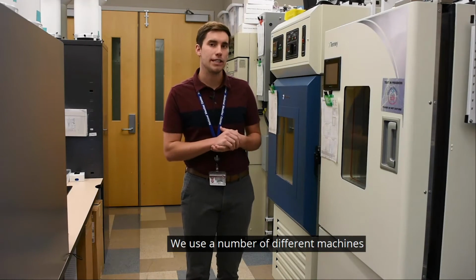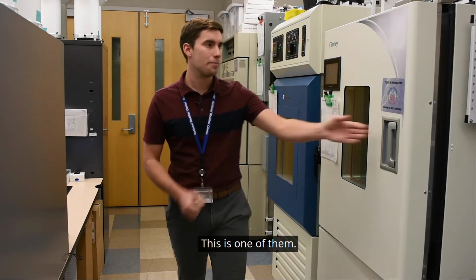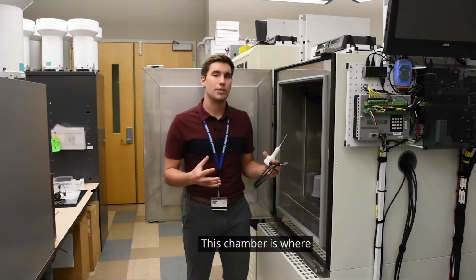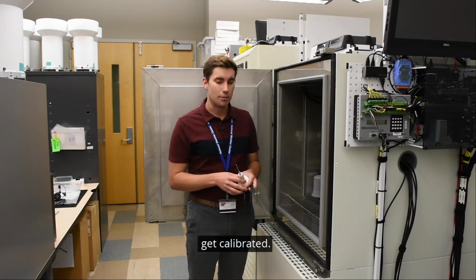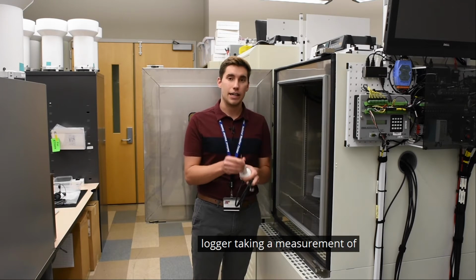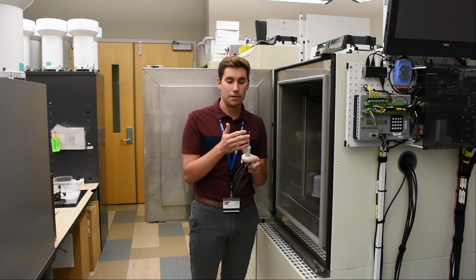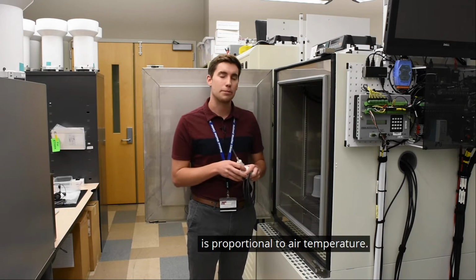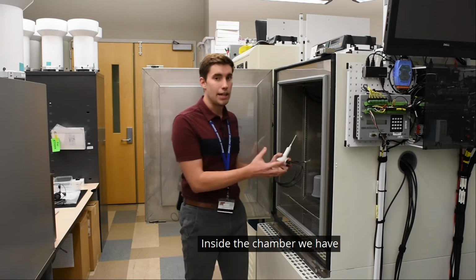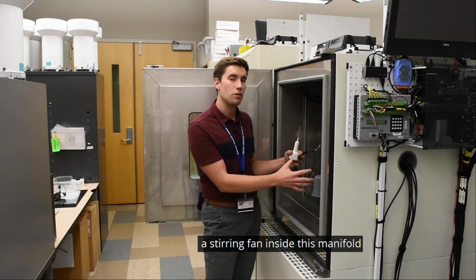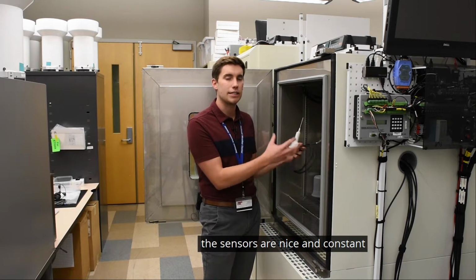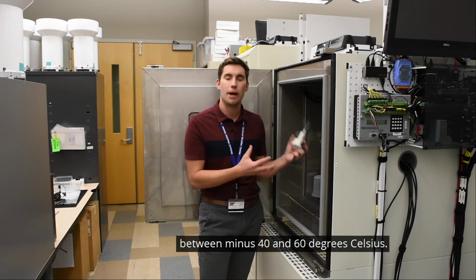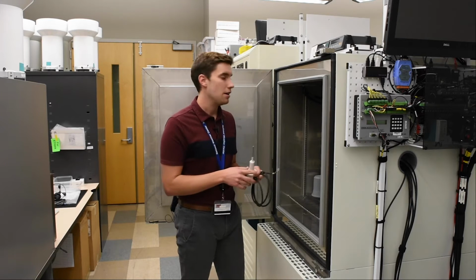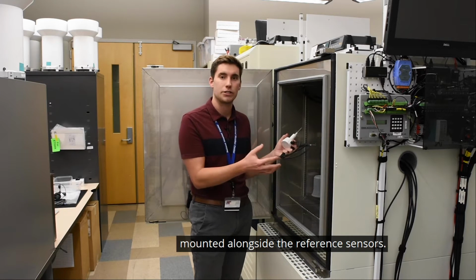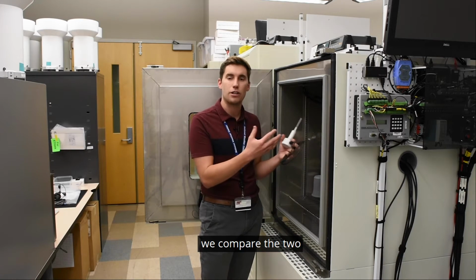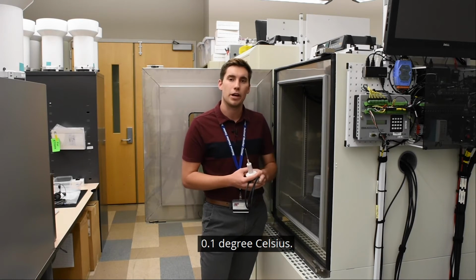We use a number of different machines in the lab to calibrate sensors. This is one of them. This chamber is where the Oklahoma Mesonet air temperature sensors get calibrated. These sensors work by the logger taking a measurement of resistance across the tip of this platinum sensor, and that resistance value is proportional to air temperature. Inside the chamber, we have a stirring fan inside this manifold, which keeps the area where the sensors are nice and constant as we change the temperature between -40 and 60 degrees Celsius. We have the test sensors mounted alongside reference sensors, and at the end of that process, we compare the two to make sure that they're within 0.1 degrees Celsius.